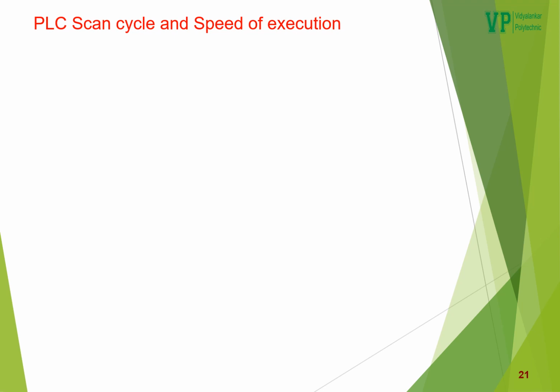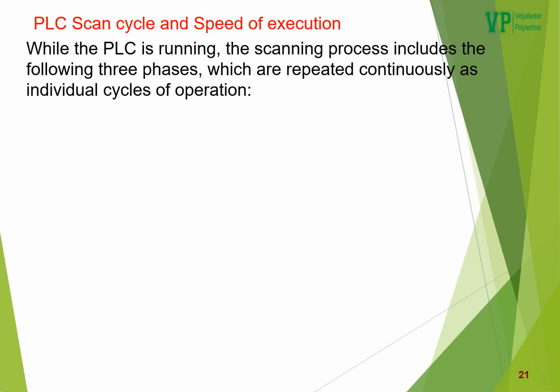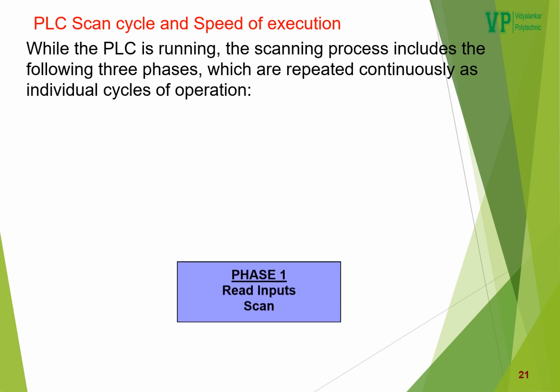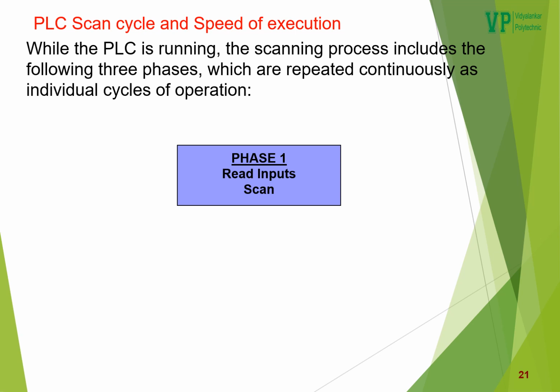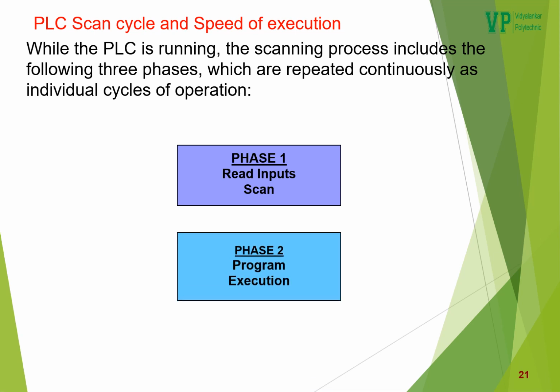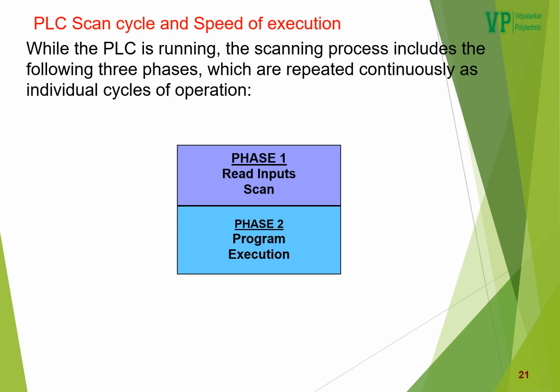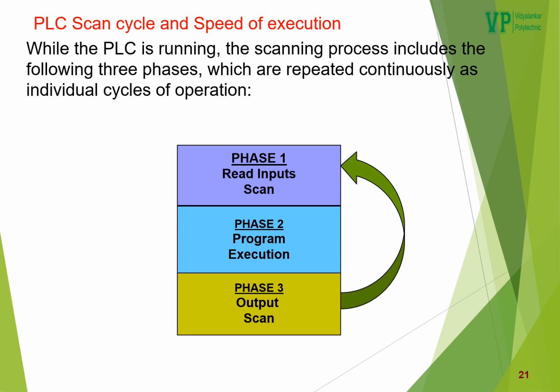PLC scan cycle and speed of execution. While the PLC is running, the scanning process includes the following three phases, which are repeated continuously as individual cycles of operation. Phase 1, read inputs scan. Phase 2, program execution. Phase 3, output scan. And then goes back to phase 1. And the process repeats. In order to understand this in a better way, let's have a look at the animation.